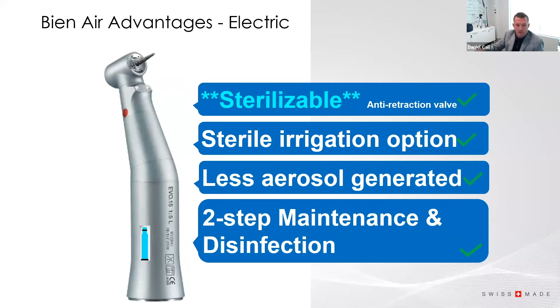So all of our Bien Air electric handpieces have the anti-retraction valve in the handpiece. Every other design has the anti-retraction valve in the micromotor, which as standard practice is not sterilized between patients. It's similar to a Coca-Cola straw. If you put your finger on the top, your finger being the anti-retraction valve, and there's any contaminant inside the straw, the liquid is not static and frozen. It's swirling and swimming around. Bacteria can bloom at a very rapid rate. It's definitely climbing and crawling up through the irrigation tube with a handpiece and contacting that anti-retraction valve. So it's very important to have it sterilizable.